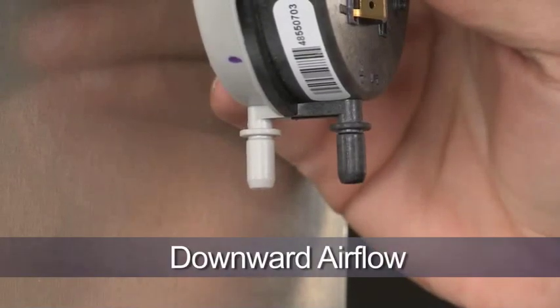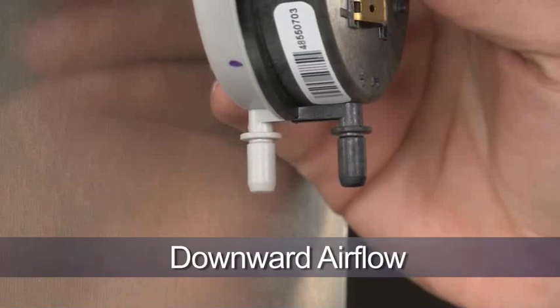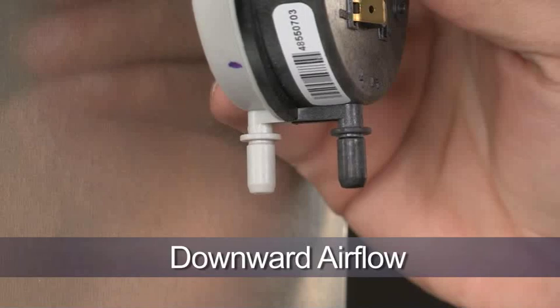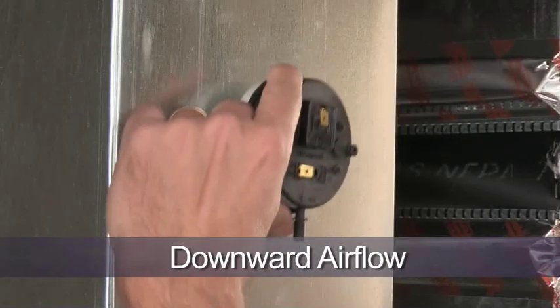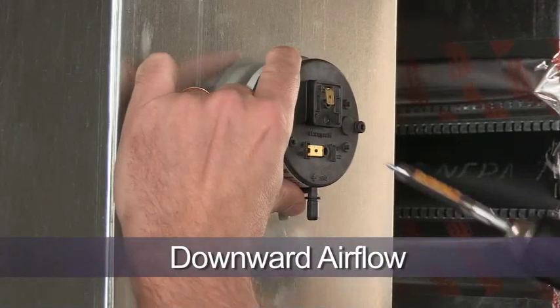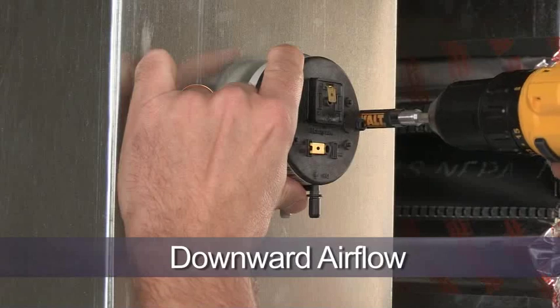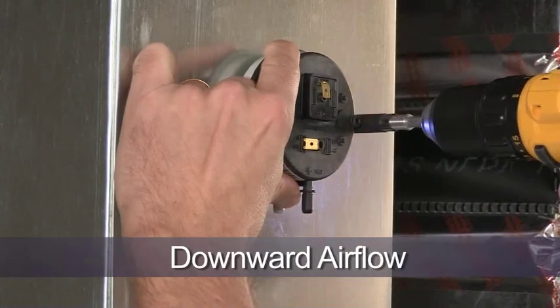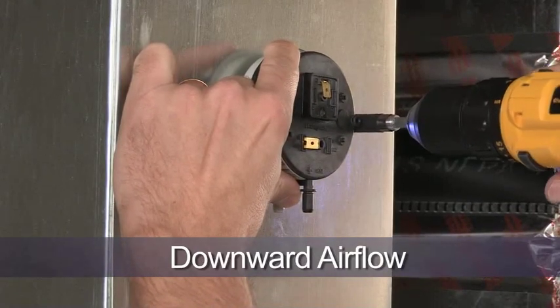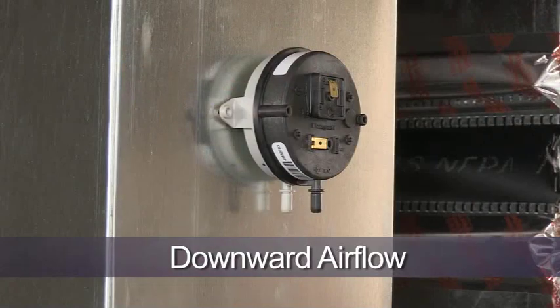Included in the box is a switch that senses air movement in the duct, indicating it is okay to introduce humidity if the humidistat control asks for it. This is referred to as the pressure switch. To begin, mount the switch vertically within 10 feet of the humidifier and both the supply and return ductwork, with the pressure connectors facing downward, as shown here. Use the provided screws to secure the switch to the duct.